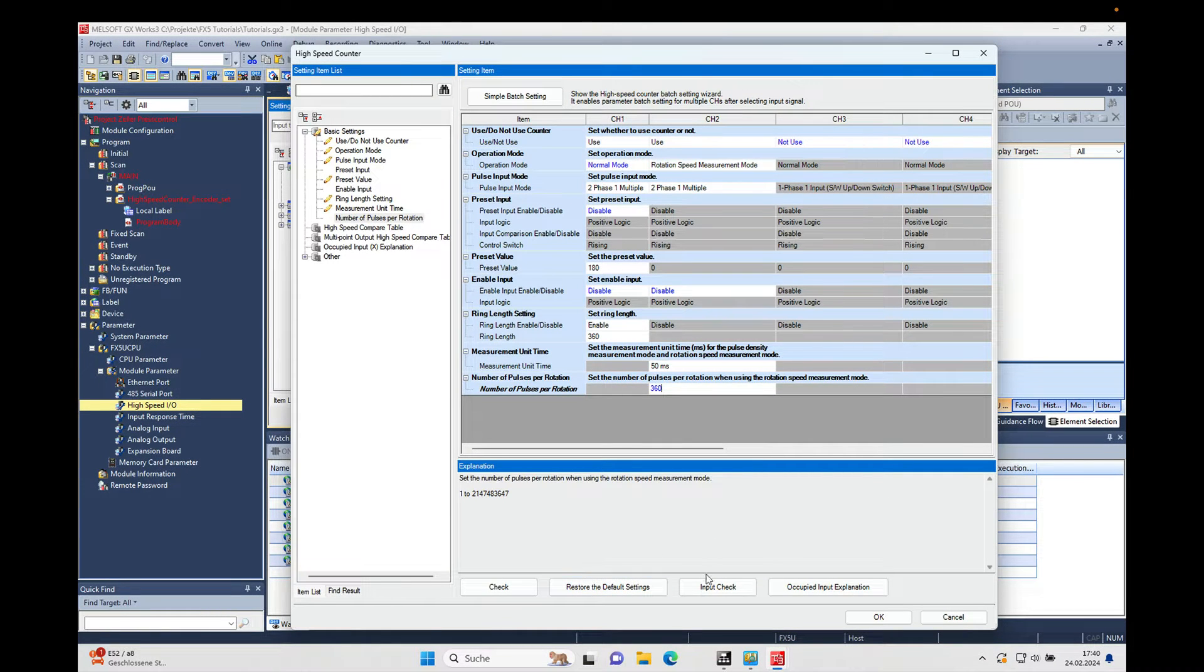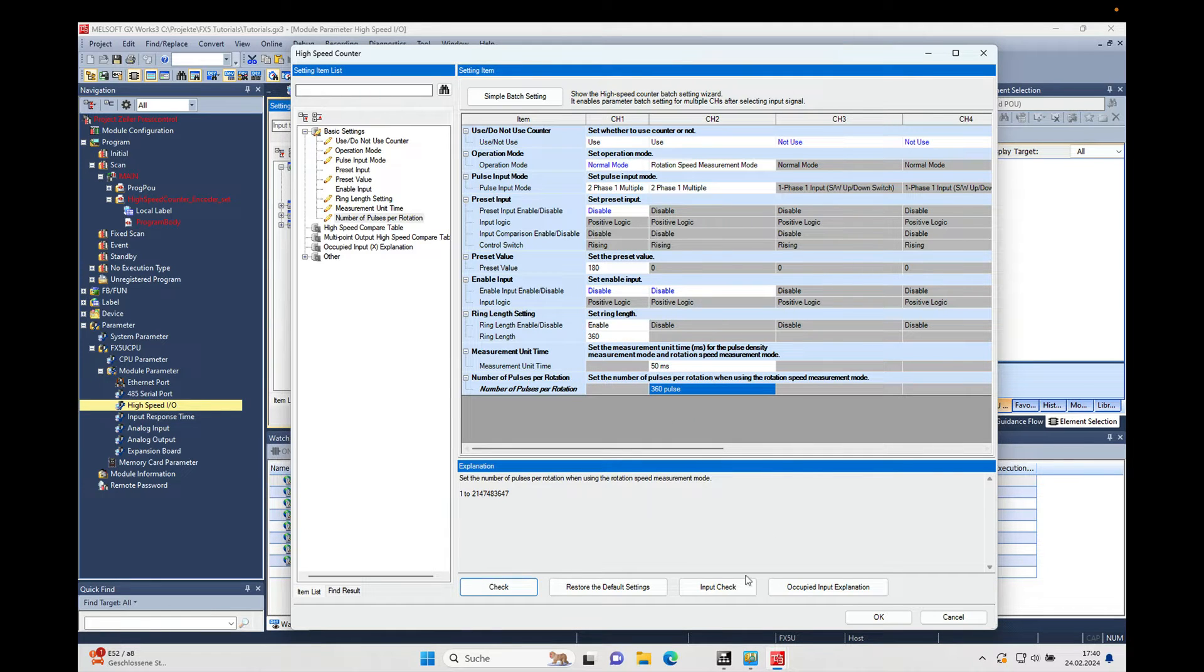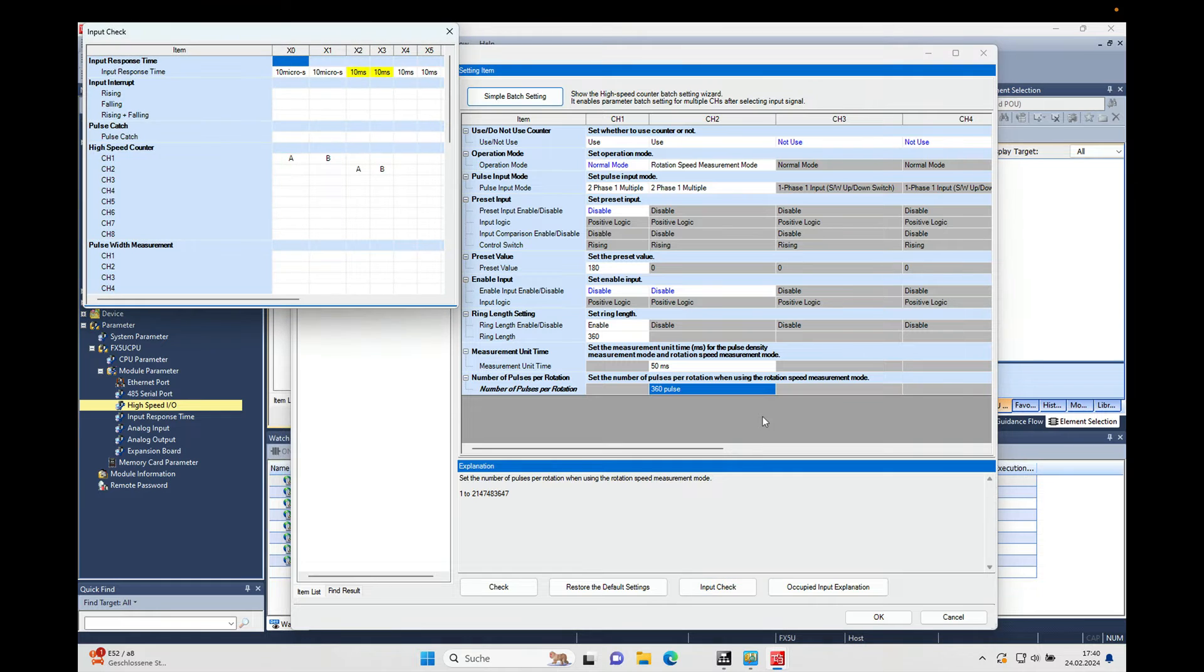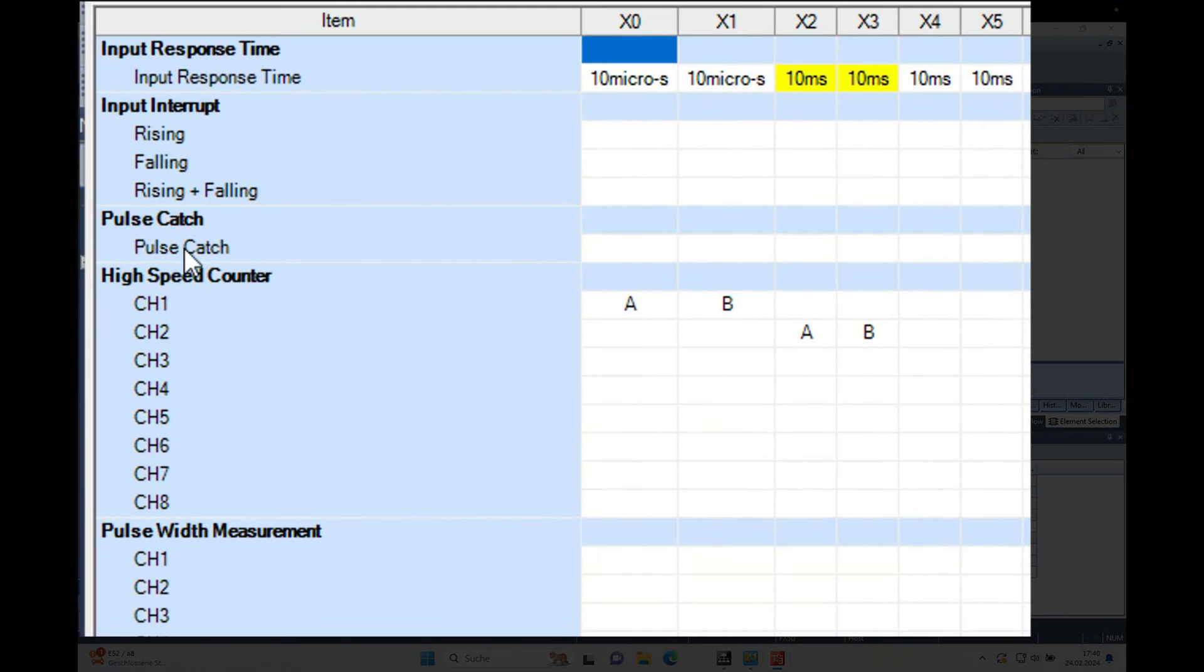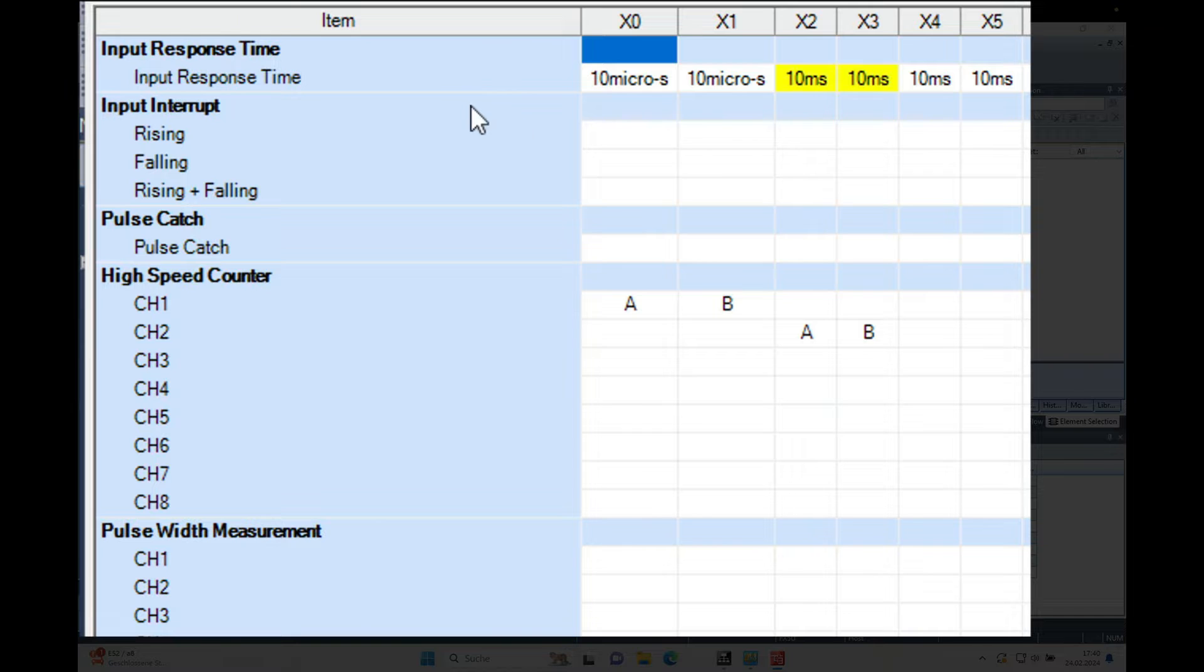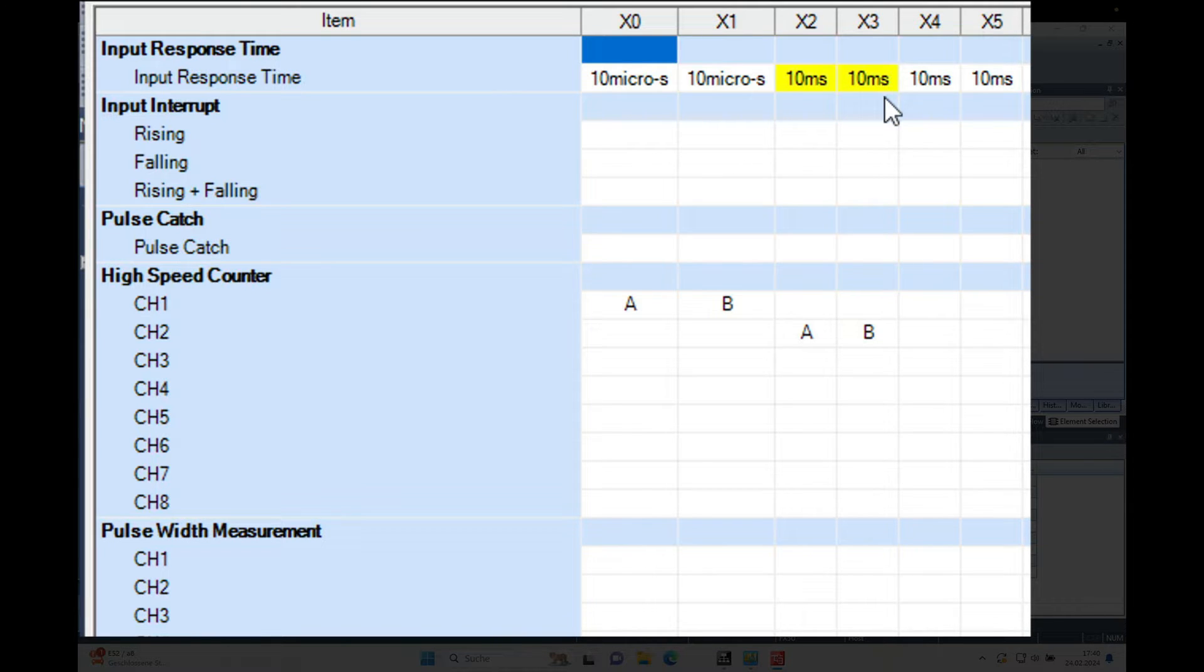The next thing is you make a check which should say no error found, there you go. And then we make an input check. And on this input check you can see that the channel 2 high speed counter uses the inputs X2 and X3, and those inputs actually are set right now to 10 milliseconds and this is way too low.